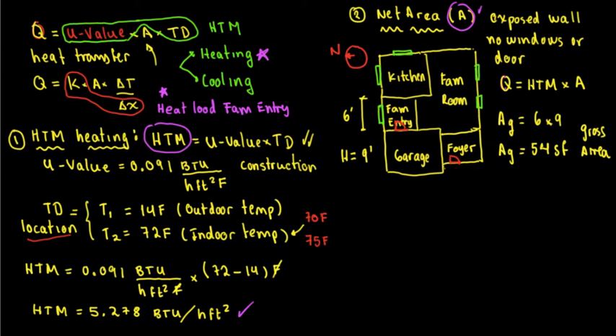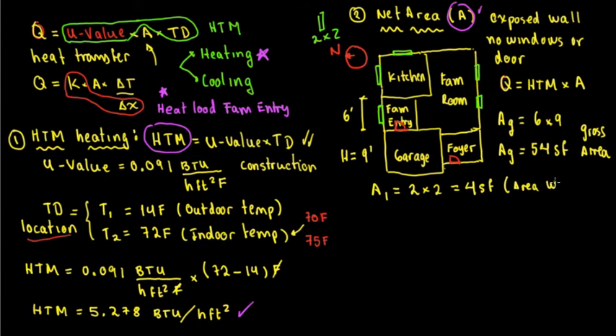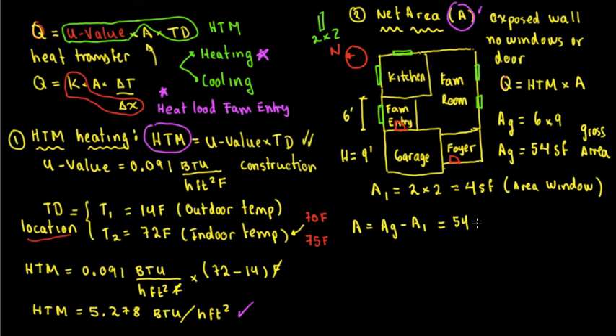The windows — we're making assumptions here — are going to be 2 by 2. So area 1, windows, is going to be 2 times 2 equals 4 square feet. That's the area of windows, which goes to the fenestration load. So the net area is going to be equal to the gross minus the windows: 54 minus 4 square feet. My net area is going to be equal to 50 square feet of exposed wall.